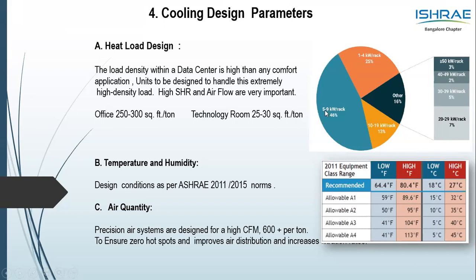So it becomes very critical that you have the right cooling unit designed, of course with the heat load designed for the room, also checking the kilowatt per rack, what is the heat load or kilowatt per rack into the number of racks, combining both of that to give you the answer of the cooling capacity required.